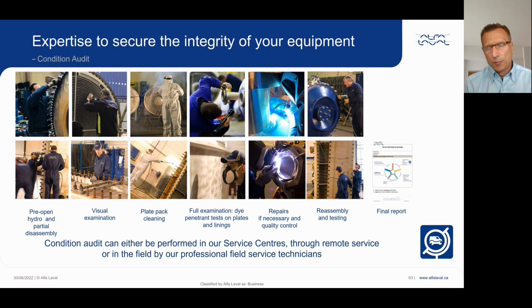The pre-open hydro is actually pretty valuable, as it will tell us if either side is failing externally or cross-contaminating. Then we'll get into a visual examination, making sure all components are in good shape and seeing if anything has to get replaced. Obviously, we'll do a good cleaning of it.